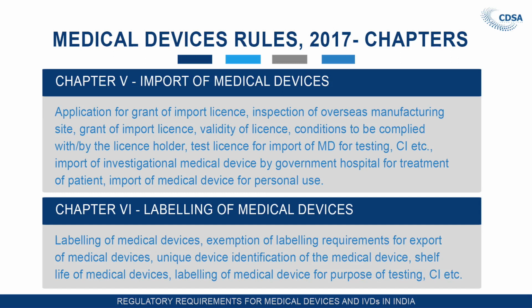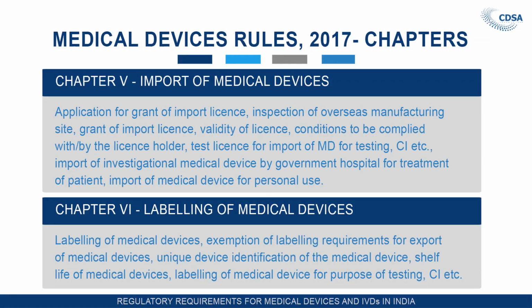The shelf life of medical devices: what will be the shelf life? Based on the stability study data submitted by the firm, the licensing authority will give approval for the shelf life of the medical devices. A maximum shelf life of five years has been given in the Medical Device Rules 2017 under this provision. However, if there is sufficient data from the stability study to prove a shelf life of the product of more than five years, based on the documents generated, the licensing authority will consider a shelf life beyond the five years provided in the Medical Device Rules 2017. Labeling of medical devices for the purpose of testing or clinical investigation.